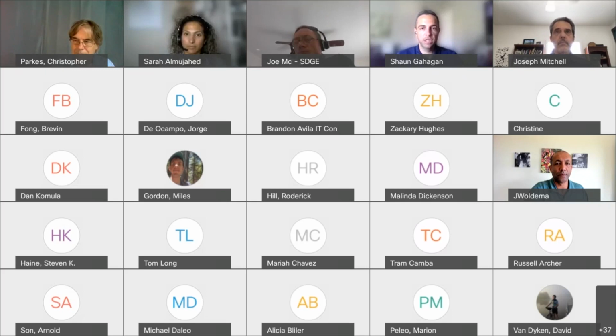The falling conductor protection continues to be implemented to more and more circuits. They started with all the tier 3 circuits, and I still believe they were on track to complete all the tier 3 circuits by 2026, I want to say is the right number. But I think in the ramp, we're on the order of 10 or so circuits per year that we'll be implementing falling conductor on moving forward. And that one does have a bit more cost to it because there is new equipment, new relaying and things that need to be installed at the substation in order to implement these things.